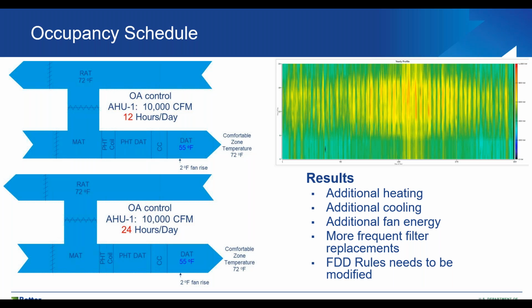And I'm showing the more energy use, but the flip side could occur also. You may have a room that's now basically off all the time, and you need to change flags to indicate, well, they were running at this schedule. Is it an override? Why is it now operating with less energy, less time? Next slide, please.